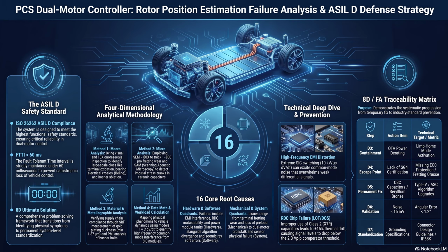Yeah, and if the software's hard-coded panic response is to execute a 3-phase freewheeling shutdown, meaning it just opens all the high-voltage switches to protect itself, that generated current has nowhere to flow except right through the anti-parallel diodes of the SiC MOSFETs, straight into the DC link capacitor. And the bus voltage skyrockets exponentially. It goes from 800 volts to over 1200 volts in milliseconds. And once that voltage exceeds the avalanche breakdown threshold of the silicon carbide semiconductor lattice, the PN junctions are completely destroyed. The modules literally vaporize. The inverter is essentially a bomb that just detonated itself because it misread a single data point. This is precisely why building an ASIL-D architecture is so incredibly complex. You are managing the physical mechanics, the electromagnetics, the quantum-level data integrity, and the software's psychological response to failure simultaneously.